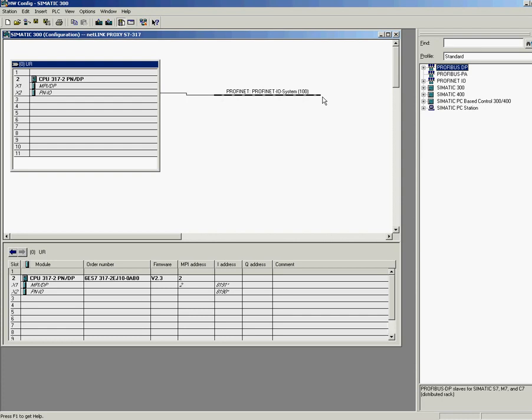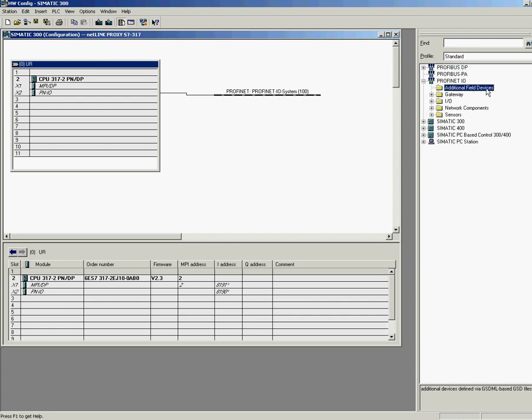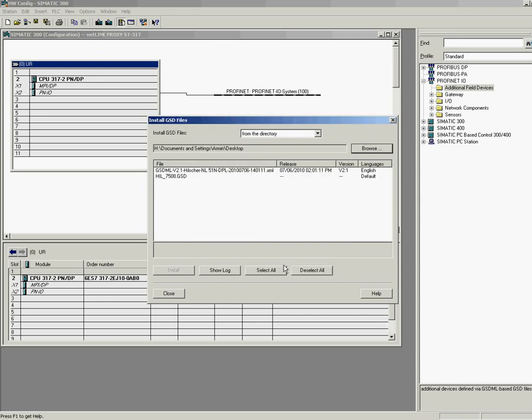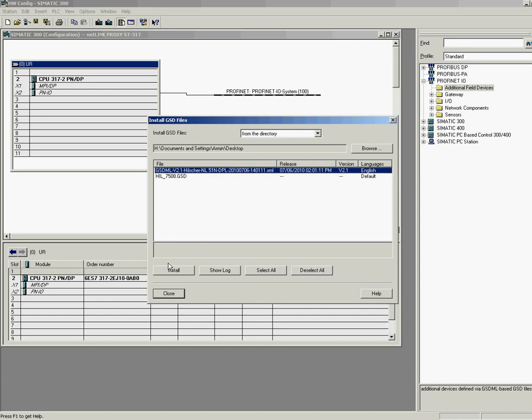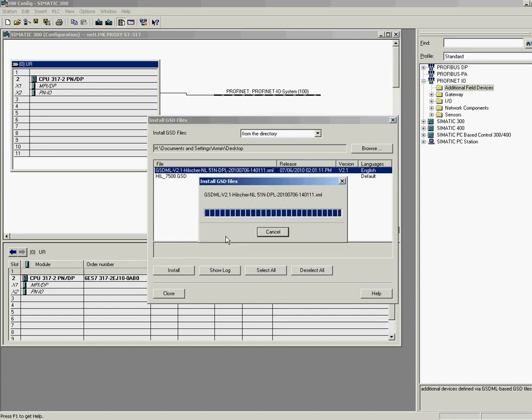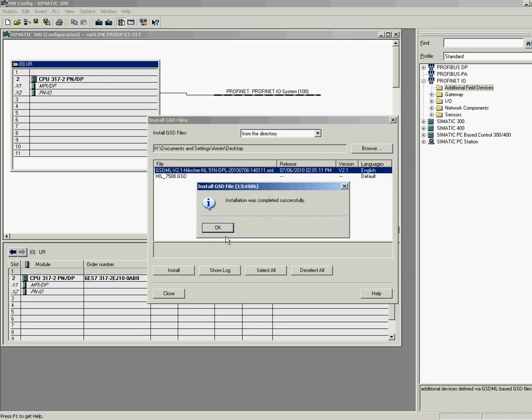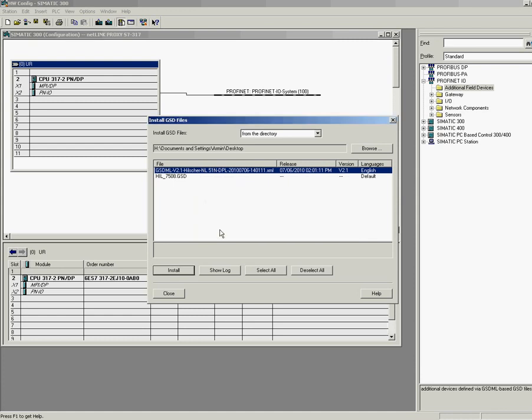What we have to do now is to import the GSDML file that I have exported previously within Sycon. Look here, the additional devices are empty. To do so, choose options, install GSD file. Move to the folder where the GSDML file is located. Step7 offers you all the options. And then choose the GSDML file. Step7 will now update its device catalog as well. This may take a while.